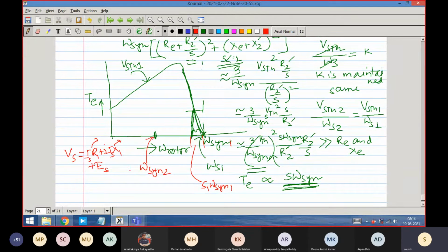X1 is the leakage inductance, very small. It is negligible compared to the level of the voltage. So Vs is essentially dictating Es. By supplying voltage, we are essentially deciding what the eventual induced voltage should be. We are asking the machine to develop it accordingly.